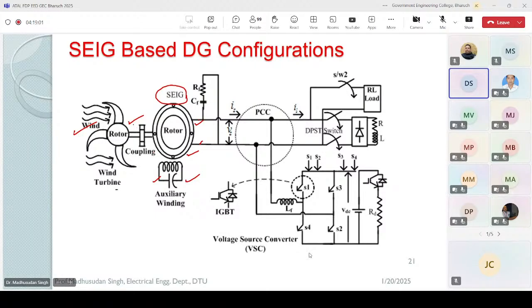That an induction machine, when driven by a prime mover and a capacitor of appropriate value is connected in the auxiliary, the machine starts generating voltage, and that is the case of an induction generator. Now this arrangement could be extended even for three-phase induction machines, where instead of a single capacitor, you need to connect a three-phase capacitor bank. And since in a three-phase squirrel cage machine, the only access is the stator, this capacitor bank is connected at the stator only, as the rotor is a squirrel cage.